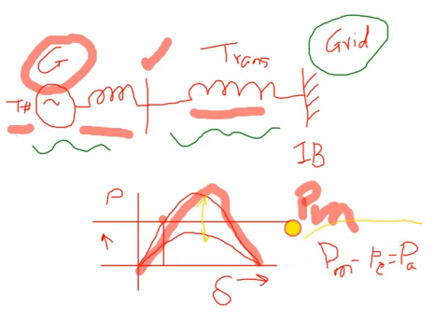Here I have written a very famous equation, the swing equation you can call it, but we are not discussing it in terms of rate of change of frequency or inertia. I have just written it as accelerating power, which is the difference between mechanical power and electrical power. Please understand, whenever a fault occurs in the system, your mechanical power remains intact because you are not taking immediate action in terms of opening and closing turbine valves.